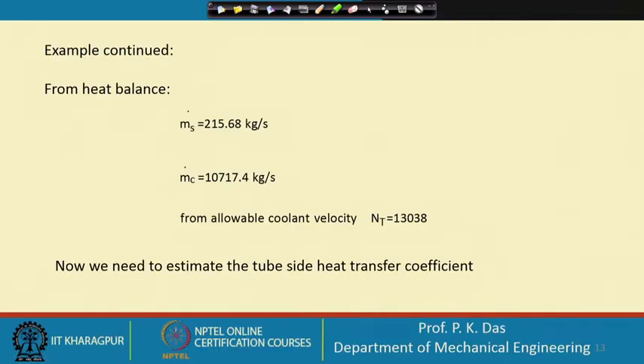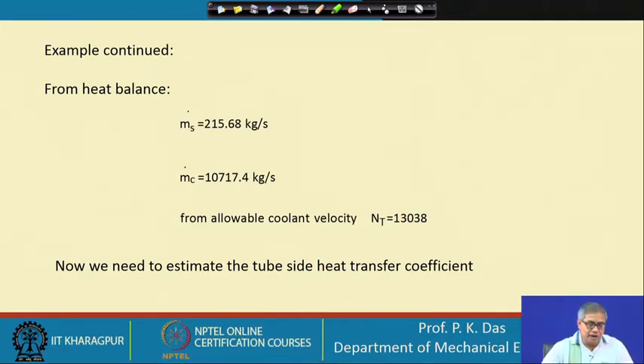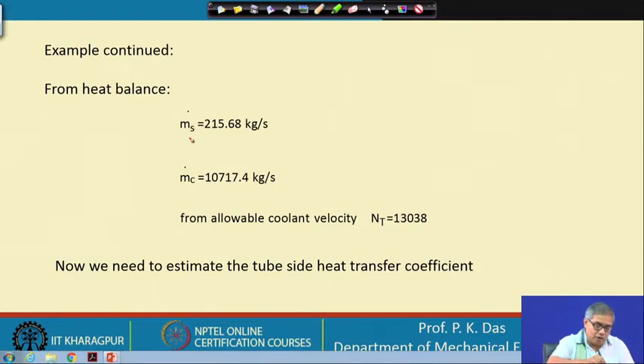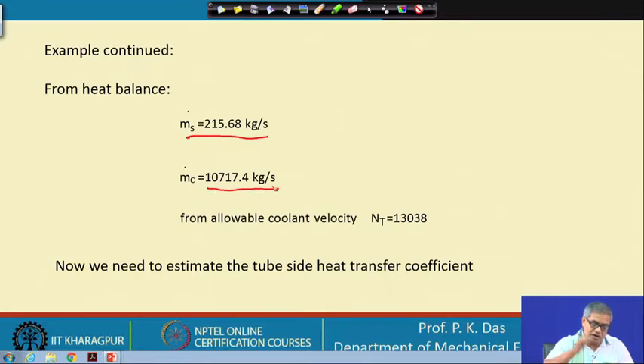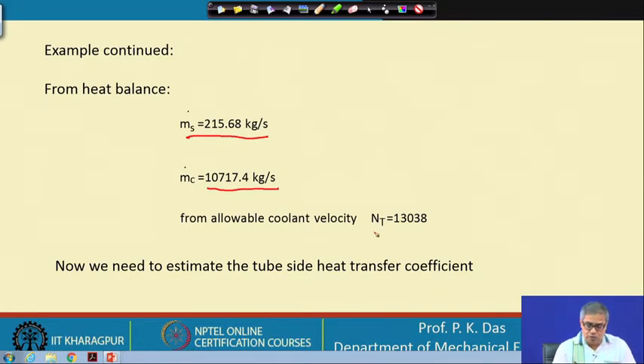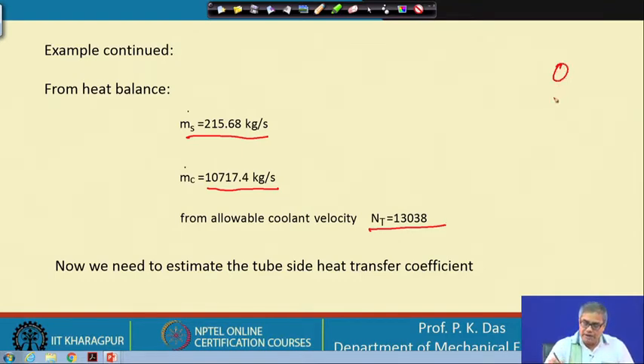Here you see the example we are continuing. From the heat balance we have got two very important quantities: the steam flow rate m-dot-s, and the coolant flow rate m-dot-c. From the allowable coolant velocity we have got N_T, that is the total number of tubes. We have assumed that on a column there will be 70 tubes.